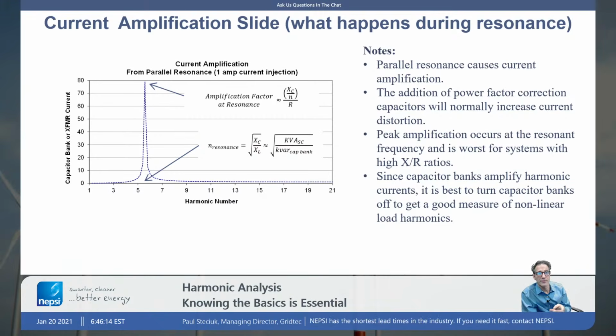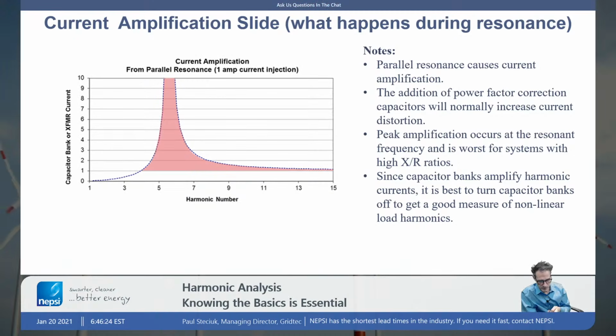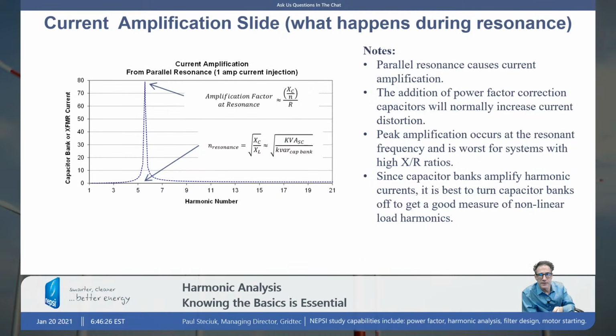One of the things that happens is you get an amplification of voltage distortion. We've been shown that. But you also get an amplification of current. Your harmonic current is amplified. So in this case, at resonance here, you can see that the current is amplified by a factor of 80.